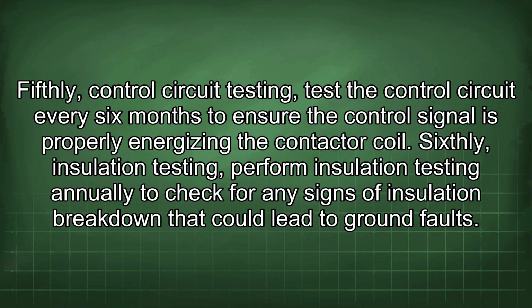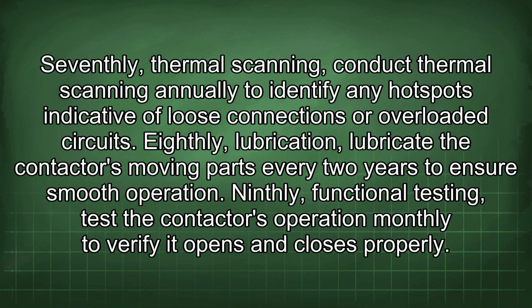Perform insulation testing annually to check for any signs of insulation breakdown that could lead to ground faults. Seventhly, thermal scanning. Conduct thermal scanning annually to identify any hotspots indicative of loose connections or overloaded circuits. Eighthly, lubrication. Lubricate the contactor's moving parts every 2 years to ensure smooth operation. Ninthly, functional testing. Test the contactor's operation monthly to verify it opens and closes properly.